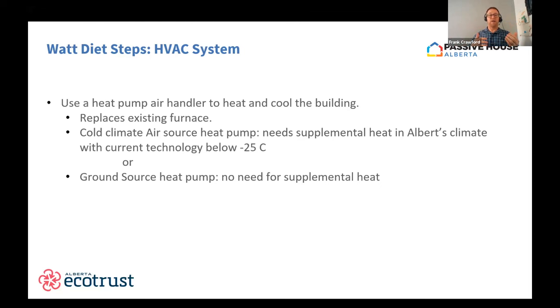And we want to then use either a cold climate air source heat pump to run the system. Right now, in Alberta's climate, because the current technology for air source heat pumps only really works down to minus 25 degrees Celsius, we're going to need some type of supplemental electric resistance heat as a backup. Or we could use a ground source heat pump that uses the ground as the heat sink. Because of that, it doesn't need any supplemental heat. But that's basically how we're changing the HVAC system, how we heat and cool our building.